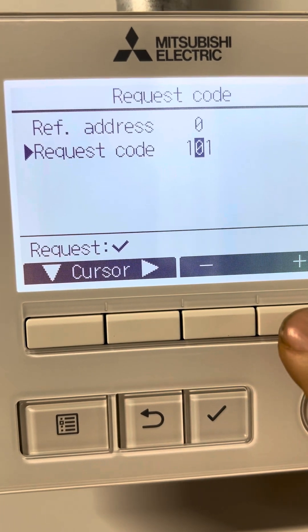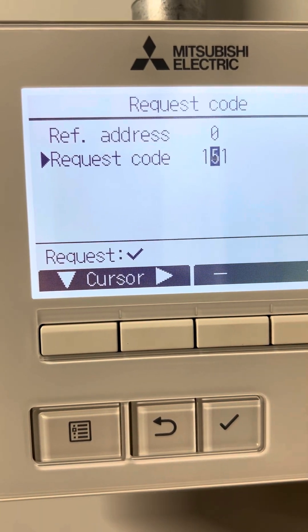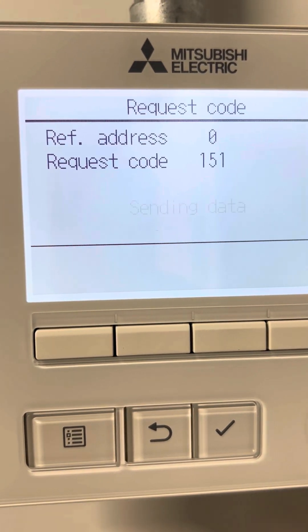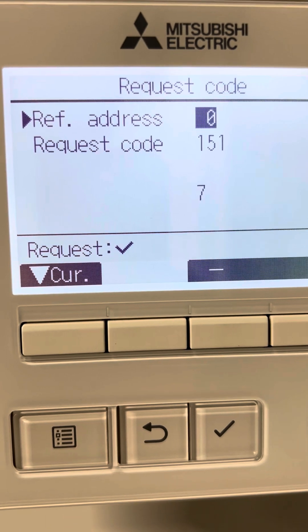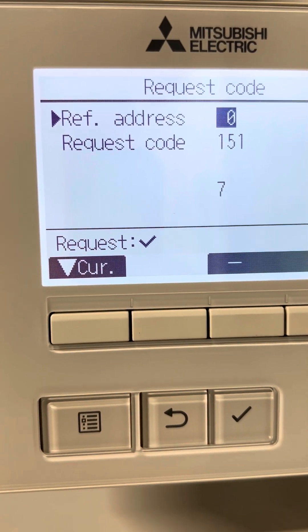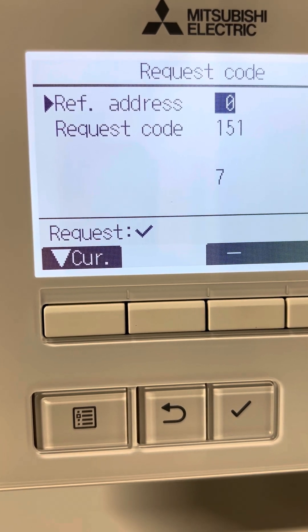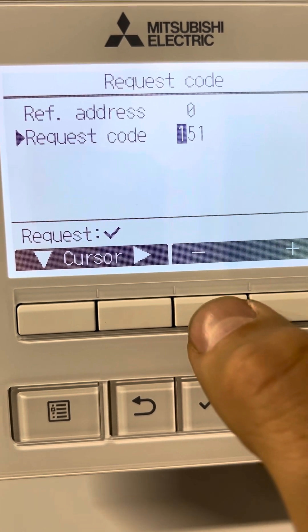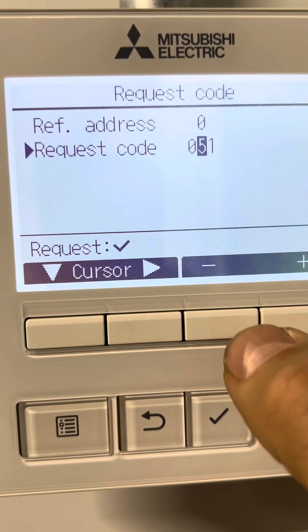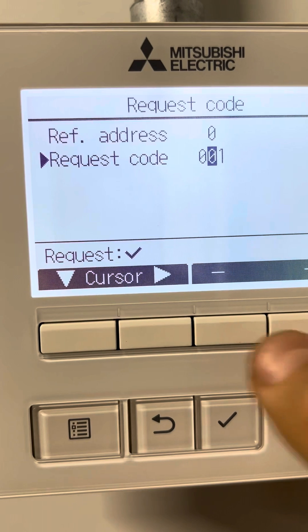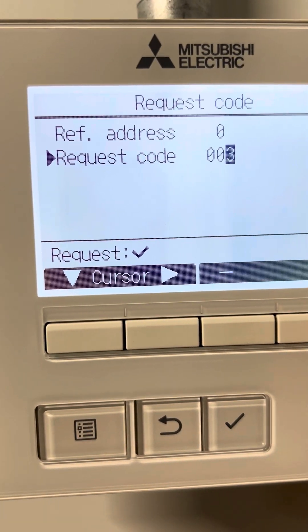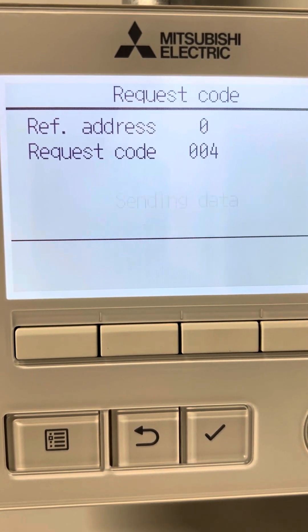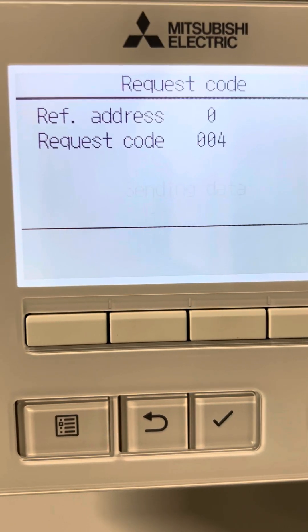For example, if I want the indoor liquid pipe temperature, the request code is 151 — it shows 7 degrees. If I want the discharge temperature of the outdoor unit, the request code for it is 4, which gives me the discharge temperature — 46 degrees.